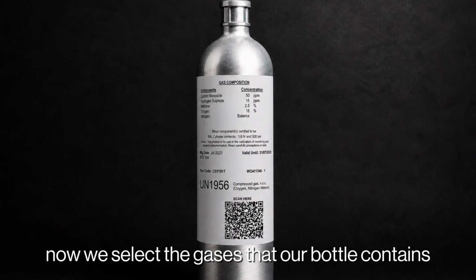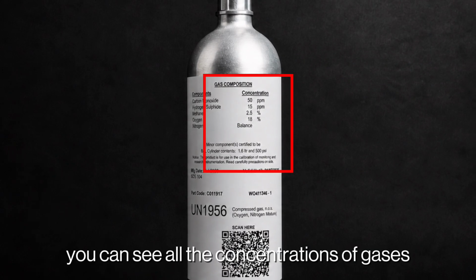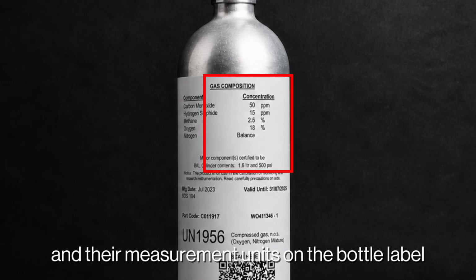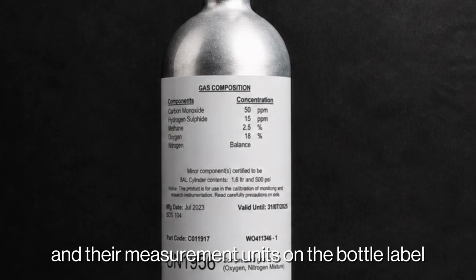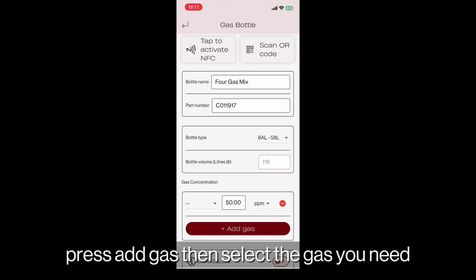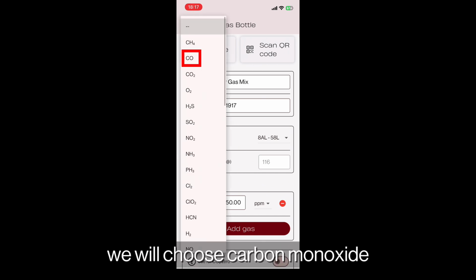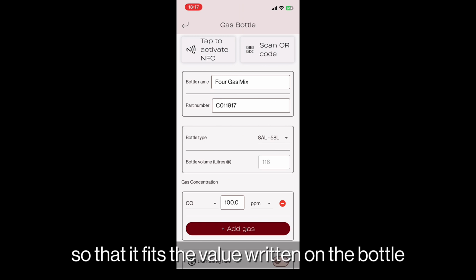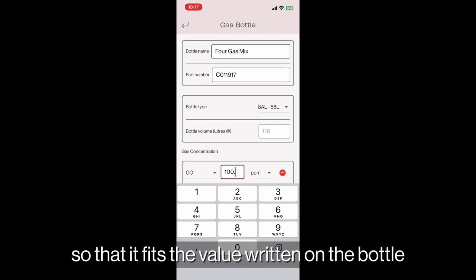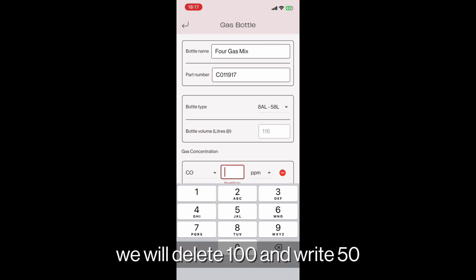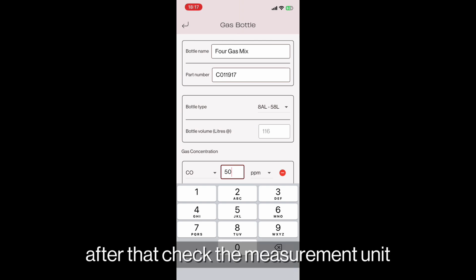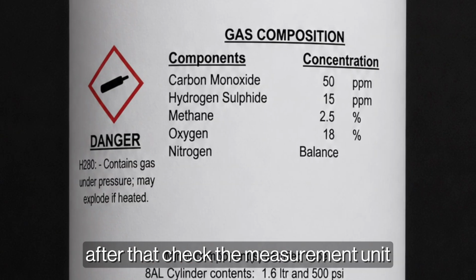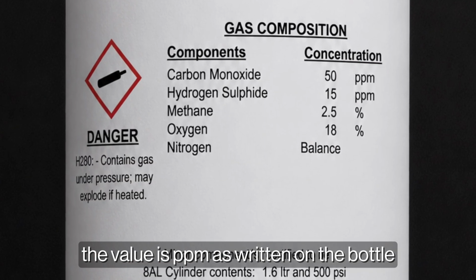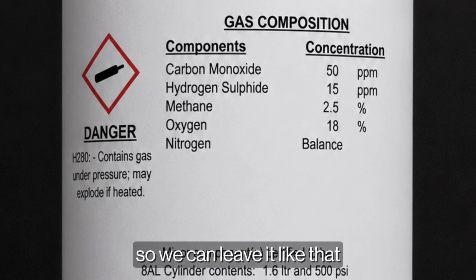Now, we select the gases that our bottle contains. You can see all the concentrations of gases and their measurement units on the bottle label. Press Add Gas, then select the gas you need. We will choose carbon monoxide. Change the concentration so that it fits the value written on the bottle. We will delete 100 and write 50. After that, check the measurement unit.